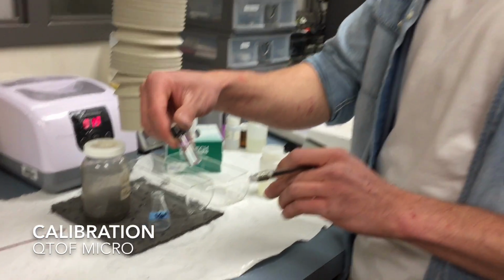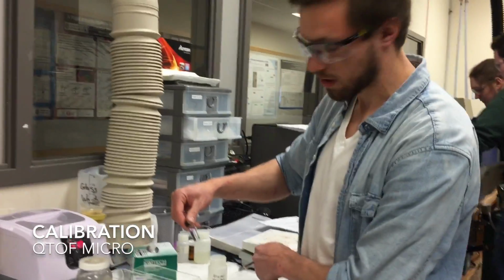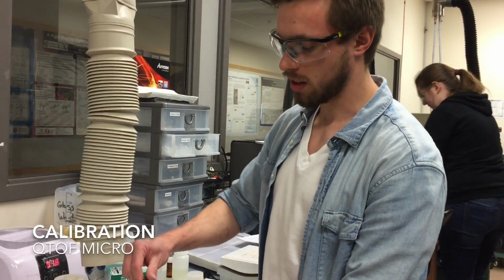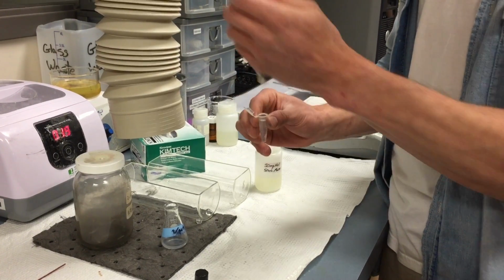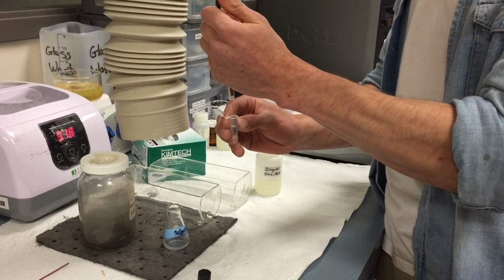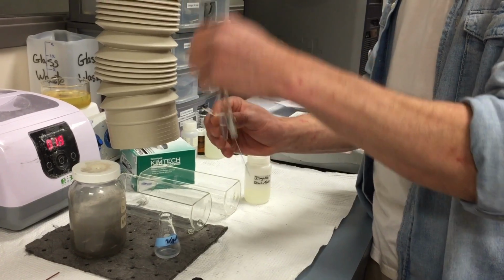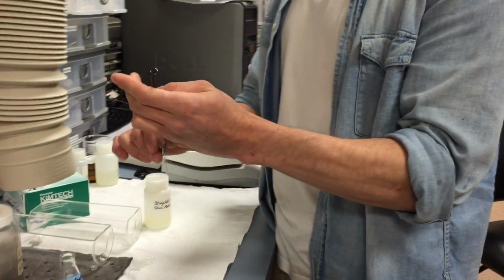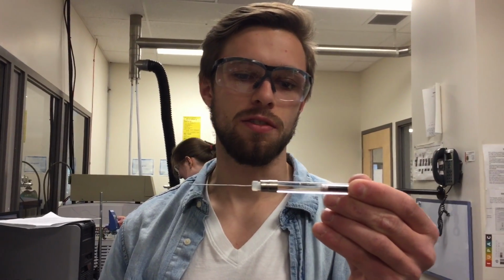It's also a good idea to rinse your syringe with whatever solvent you're going to use. In this case, it's methanol because of the solution. That also prevents further contamination. About half a milliliter is usually a good volume to calibrate with, so it doesn't run out while we're doing this.